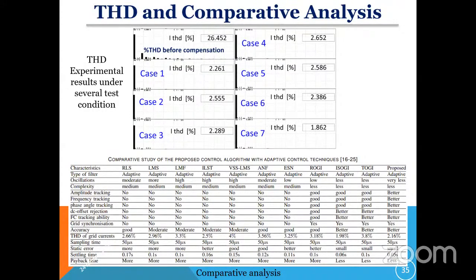In all the test cases, we got less than 5%, and that is required because, based on the IEEE 519 standard limits, we have to maintain the voltage or current THD less than 5%. So in all the conditions we have maintained the THD within the limit.